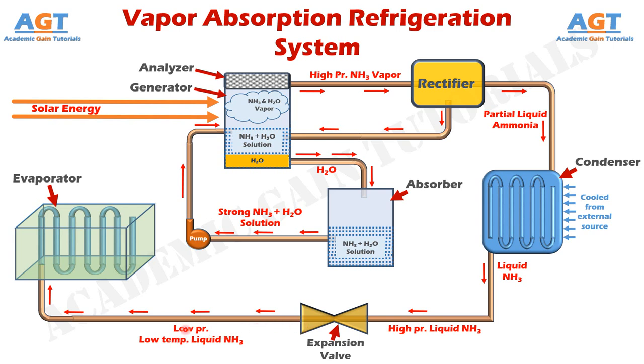Then, this liquid ammonia will be passed over to the evaporator. We all know that the main cooling effect or refrigeration effect always occurs in the evaporator. So, when this low pressure, very cold, chilled, low temperature liquid ammonia enters the evaporator coils, it will absorb all the heat present in the surface of the evaporator coils. By absorbing all the heat from the surrounding surface of the evaporator coils, this cold chilled liquid ammonia will turn into low pressure ammonia vapor inside these coils, and the surrounding surface of the evaporator will become cold by losing the heat to this liquid. Thus, the cooling effect or refrigeration effect has occurred in the evaporator.